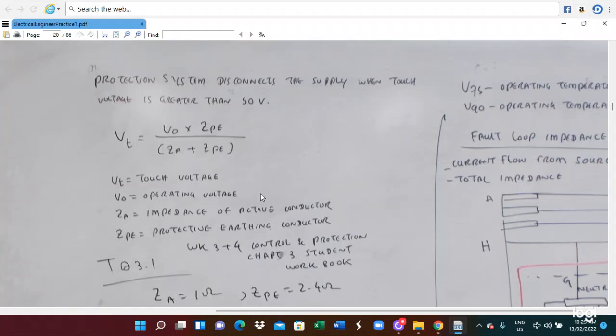VT is the touch voltage. VO is the operating voltage. This means a 240 volt system or single phase. ZPE means the protective earthing conductor's impedance, and ZA means the impedance of the active conductor. So this formula is utilized. We use this formula to determine the touch voltage.